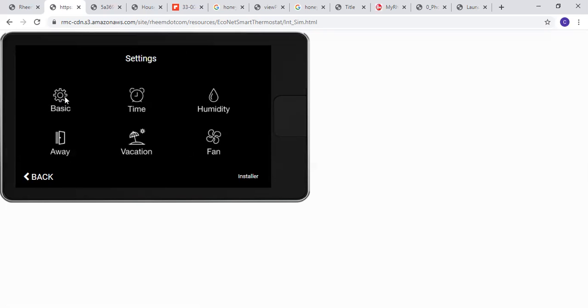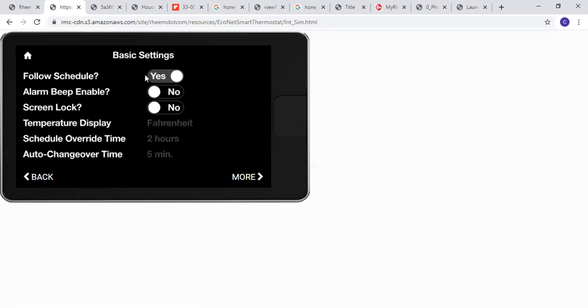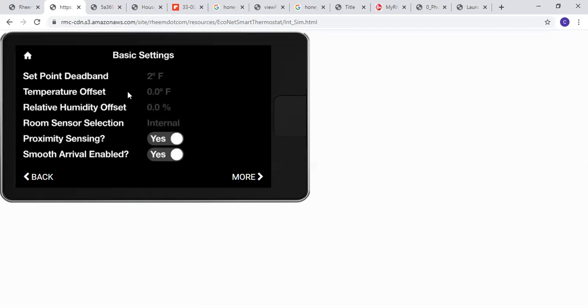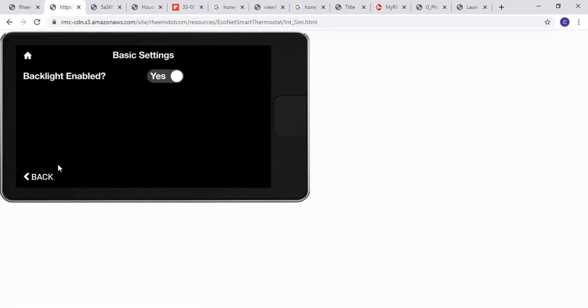So if we go into our basic here, we can follow a schedule. If we don't want to follow a schedule, just turn this off. It's even got an alarm beep, screen lock, Fahrenheit, Celsius, override, auto changeover, your dead band. You can set up a temperature offset if you wanted to, as well as a relative humidity offset. You have the option to use the internal sensor of the thermostat, or you can actually set up for a remote sensor. It has proximity sensing as well as smooth arrival enabled. And you can enable the backlight.